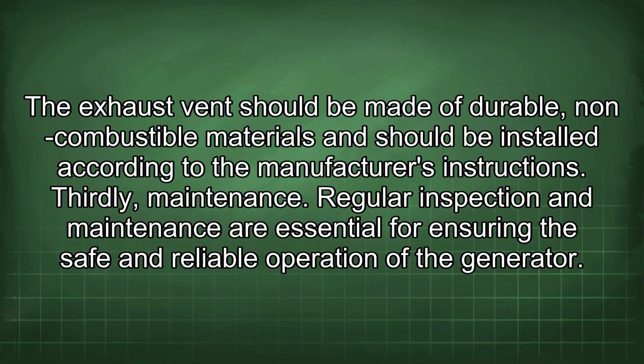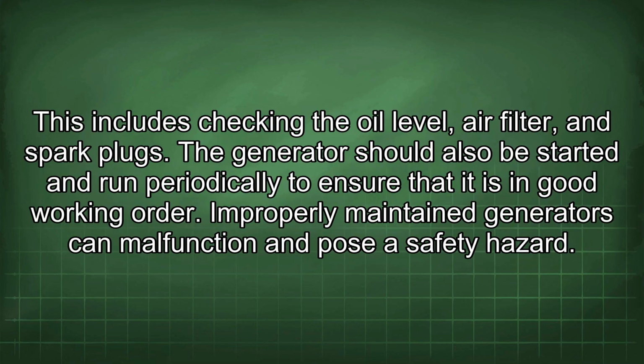Thirdly, maintenance. Regular inspection and maintenance are essential for ensuring the safe and reliable operation of the generator. This includes checking the oil level, air filter, and spark plugs. The generator should also be started and run periodically to ensure that it is in good working order. Improperly maintained generators can malfunction and pose a safety hazard.